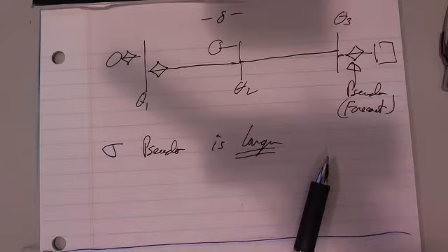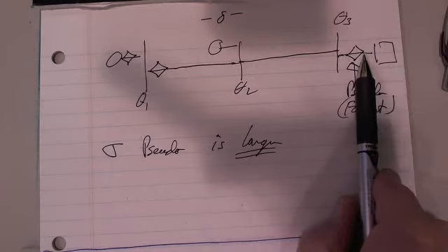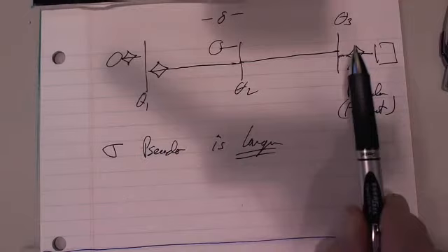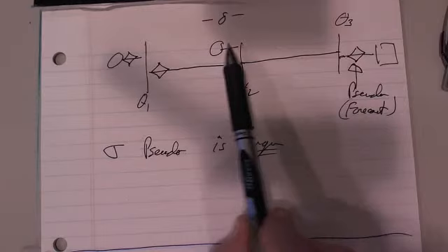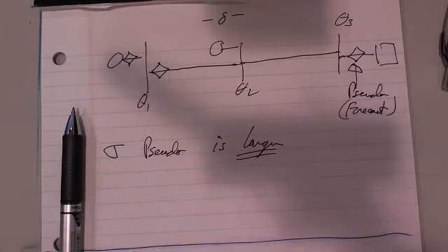And there's a lot of talk about the fact that a pseudo measurement, can it corrupt? The answer is no, it can't corrupt these two, but whatever value we put here is going to directly affect theta 3. And therefore, when I go back to solve the flow on this line and the output of this generator, it's going to be affected by any errors on that pseudo. Well, the pseudo could be off by quite a bit because it's a forecast. Suppose the load on that bus is much different for a Thursday afternoon at 4:46 like it is right now. Then it's much different than my forecast. Well, then I get a big error.